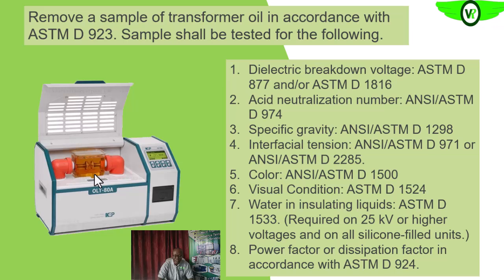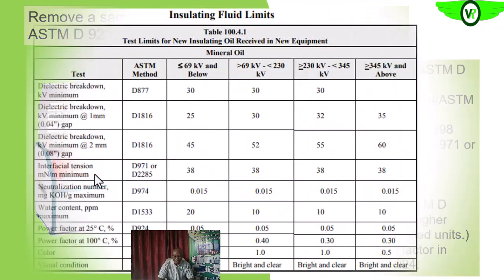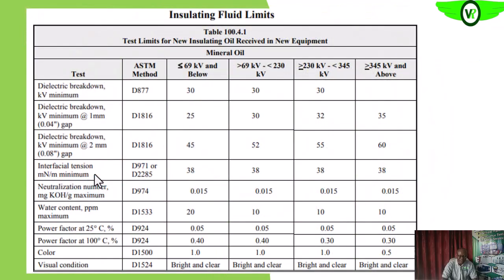So all of these tests, we'll do them according to those standards that you are seeing on the screen. That is what we want to do, and we want to ensure that they meet the right specification. So for the dielectric breakdown test, if we do not have any that is specified by the manufacturer or in our facility, we can use this as a guide. For mineral oils, below 69 kV, this is the breakdown voltage that is acceptable.